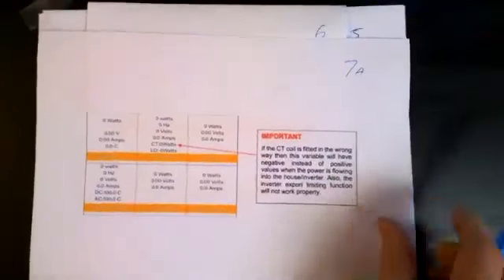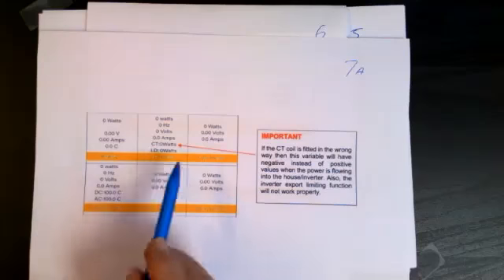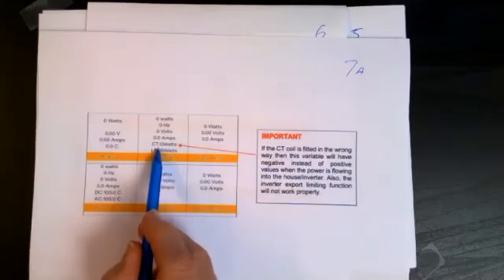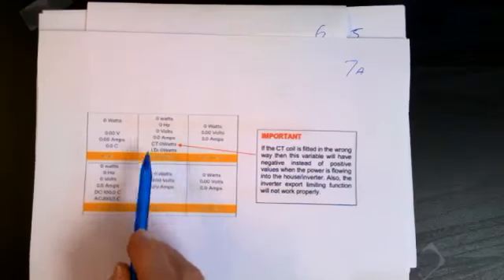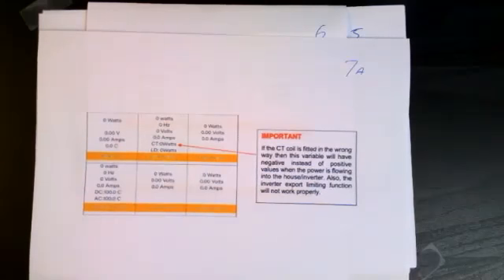I go on and on about the CT coil. One of the things is here it says CT coil. If this is a negative when it clearly shouldn't be a negative, then the CT coil is backwards. Again, it's a common problem. People often do have it backwards. And we always pick up on it.